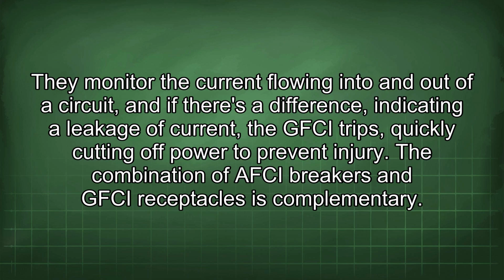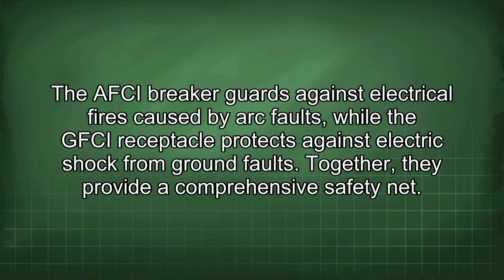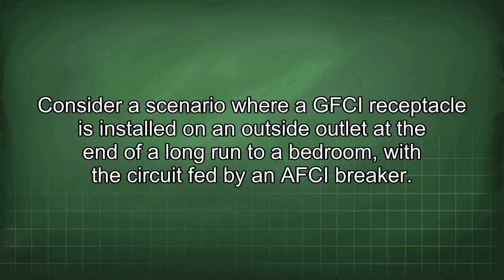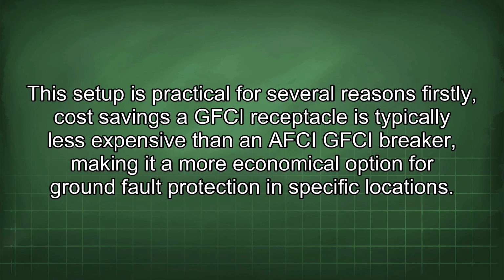The combination of AFCI breakers and GFCI receptacles is complementary. The AFCI breaker guards against electrical fires caused by arc faults, while the GFCI receptacle protects against electric shock from ground faults. Together, they provide a comprehensive safety net. Consider a scenario where a GFCI receptacle is installed on an outside outlet at the end of a long run to a bedroom, with the circuit fed by an AFCI breaker. This setup is practical for several reasons.